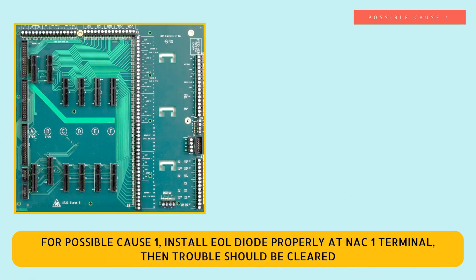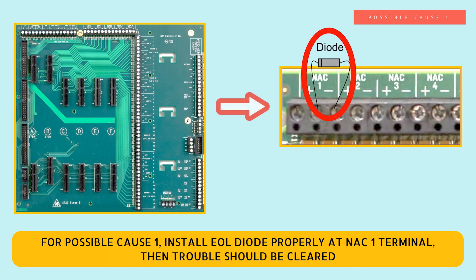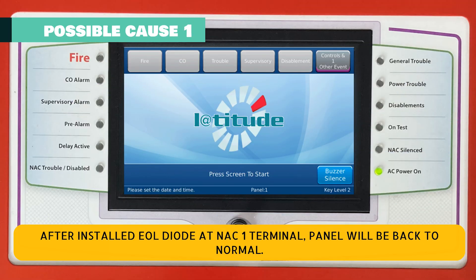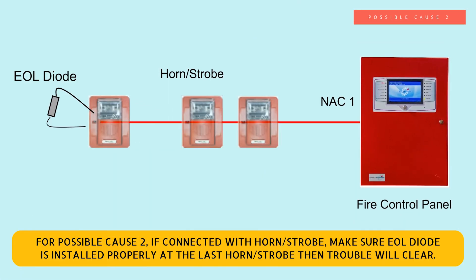For possible cause one: install the EOL diode properly at the NAC1 terminal. The trouble should be cleared after installation. Once the EOL diode is installed at the NAC1 terminal, the panel will return to normal.